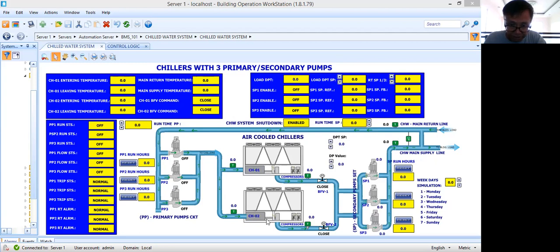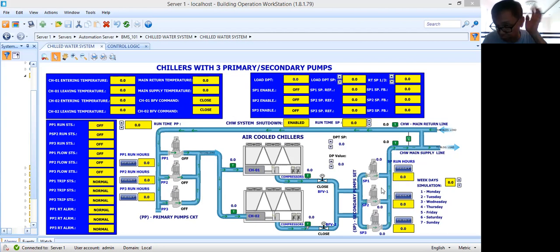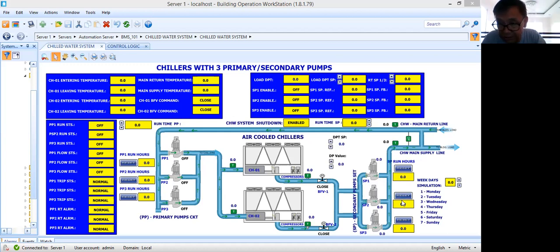This system is composed of two air-cooled chillers, three primary pumps, and three secondary pumps. The purpose of the primary pump is to pull back the chilled water supply to the building load. The secondary circuit pump job is to supply the chilled water requirement of the building. The number of pumps running will depend on the design — maybe three pumps should work at the same time if two are not big enough to handle the building load. As I said, it will be based on the mechanical design.